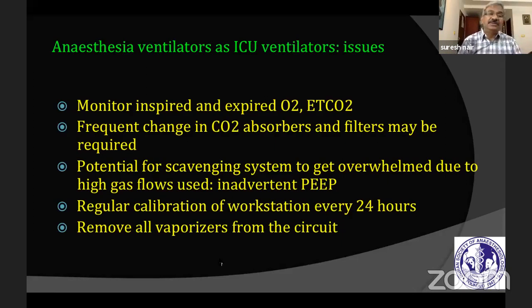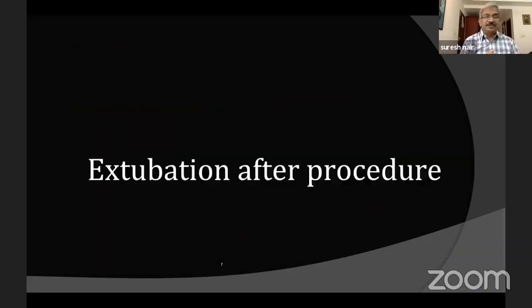Another important thing is that when we use anesthesia machines as ICU ventilators, it has to be recalibrated every 24 hours, which means you have to disconnect the patient from the ventilator, subjecting them to higher risk of hypoxemia. Finally, remove all the vaporizers from the circuit because somebody might inadvertently start an inhalation agent for these patients.